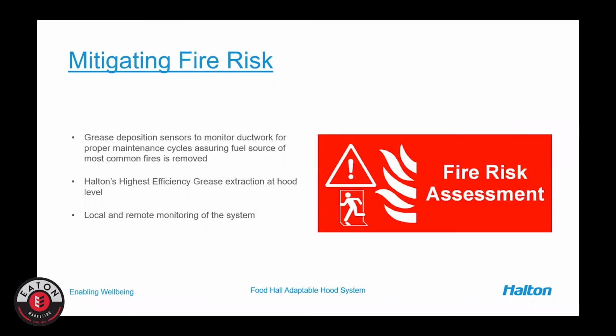So as far as the mitigation of fire, we have a couple of different solutions that we would typically look to for food halls. We have grease sensors that we install at the hoods themselves. So we would look to a high efficiency filter in the hood, perhaps even a continuous mist section or ultraviolet light in the hood for grease destruction, depending on the application. But we have a grease sensing system that we would mount in the hood collar that identifies quantifiable buildup of grease at each individual hood as well as the main trunk, and tells us that as that grease builds up, we need to clean our ductwork.